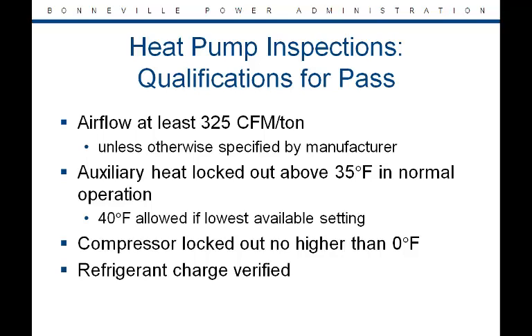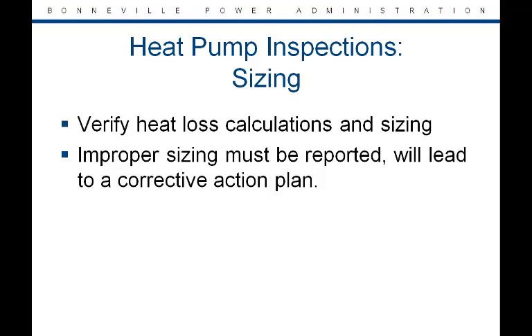Finally, refrigerant charge must be verified using the temperature split method or the line set method as outlined in the QA reference manual. Correct sizing for heat pumps is required by the PTCS installation standard. During your inspection, verify heat loss calculations and sizing. Improper sizing must be reported to the utility and to BPA, and will lead to a corrective action plan.